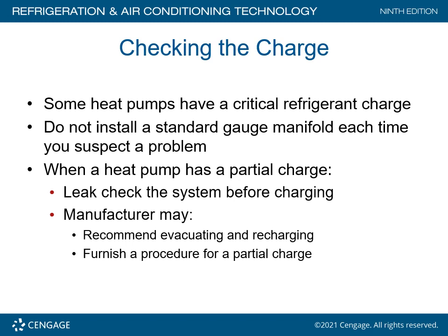Well, how do I know that? Because I told you earlier in the program, we should be seeing close to 100 degrees Fahrenheit coming out of that supply register. So if I were to put my gauge manifold set on the heat pump in the heating mode, it will indicate that I do have insufficient refrigerant to make this thing work properly. So what's the solution? Find and fix the leak. You may have to pull the entire charge out and put in a new refrigerant charge, or you could add to it. But the problem is, heat pumps have to be charged to a correct pressure-temperature relationship, just like a standard air conditioning unit. If you don't pay attention to the charging charts and manufacturer's recommendations, you can overcharge a heat pump and cause it to fail prematurely.